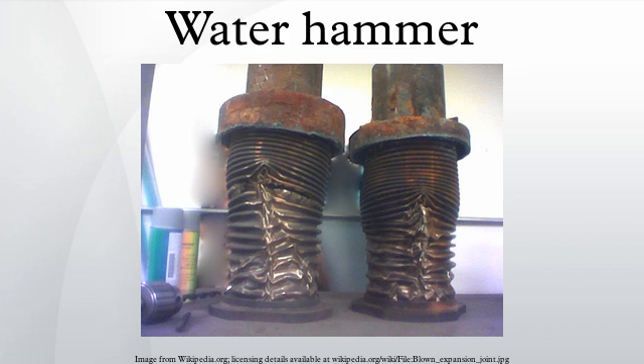As a result, we see that we can reduce the water hammer by increasing the pipe diameter at constant flow, which reduces the velocity and hence the deceleration of the liquid column. Choosing to use a material with a reduced Young's modulus. Introducing a device that increases the flexibility of the entire hydraulic system, such as a hydraulic accumulator. Where possible, increasing the percentage of undissolved air in the liquid.